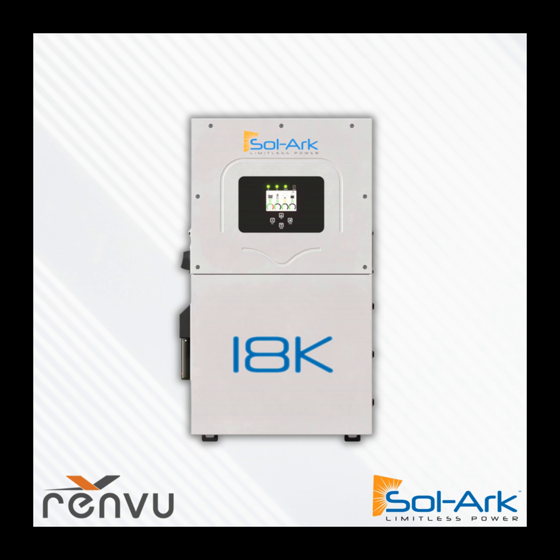But if you're experienced with the 15K, you'll know for half an hour or even longer, as long as your batteries are at a healthy state of charge, it can do longer, not continuous duration, but longer durations above 12K. With the 18K, you don't have to worry about any of that. It's an 18 kilowatt nameplate inverter with or without solar, and that is an AC output rating.